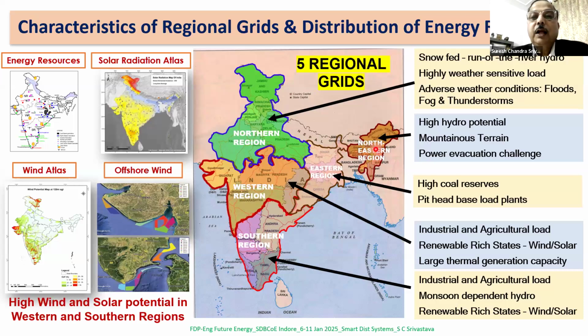So that is the reason we had gone for 800 kV HVDC coming from the northeastern region, and it is multi-pole—one line goes to the southern side, other line goes to the northern side. That is the highest DC voltage, HVDC voltage, we have in the world. China also has 800 kV DC. This single line can carry 6,000 megawatts capacity. As an AC counterpart, we have also conceived 1200 kV AC. One line is already there, but it is being operated at a lower voltage.